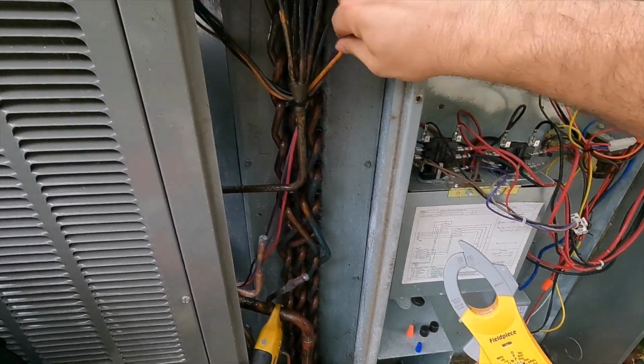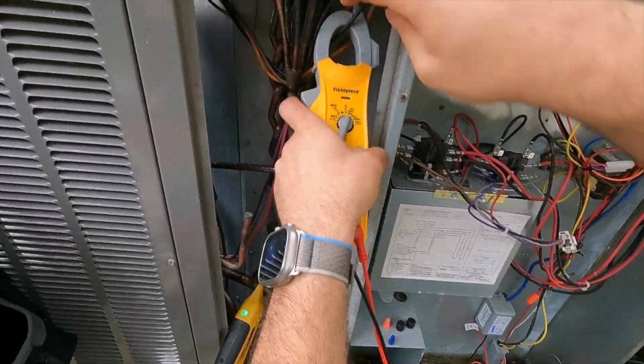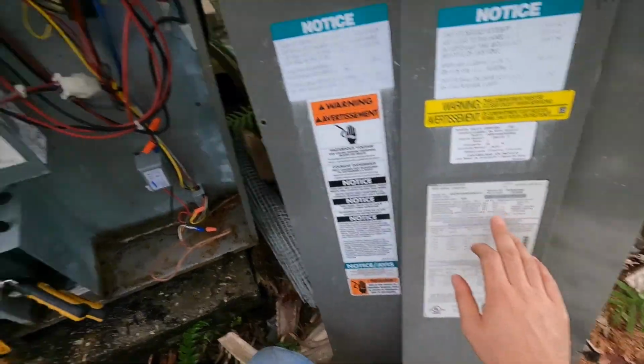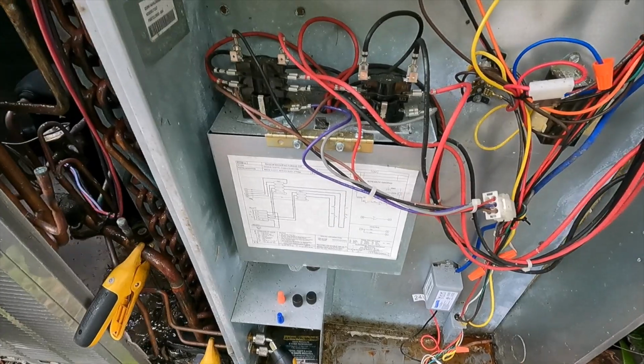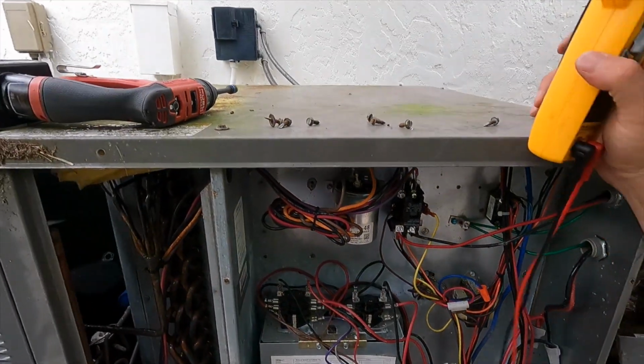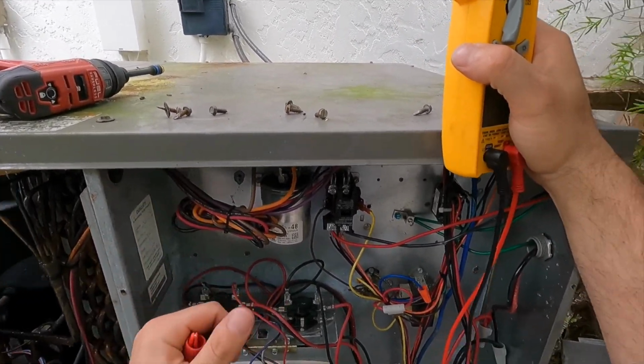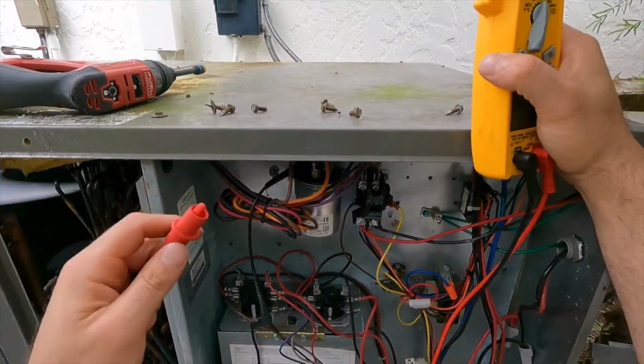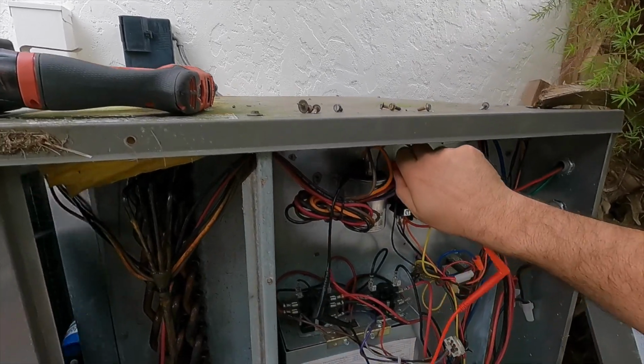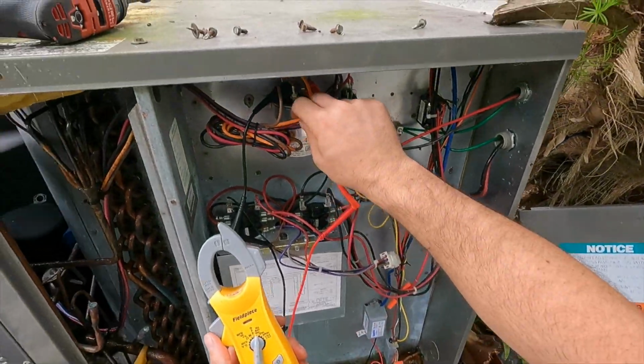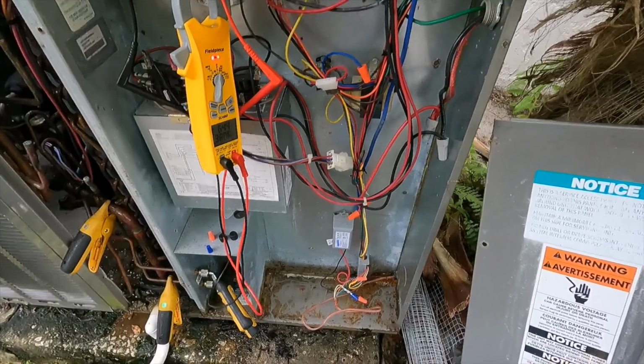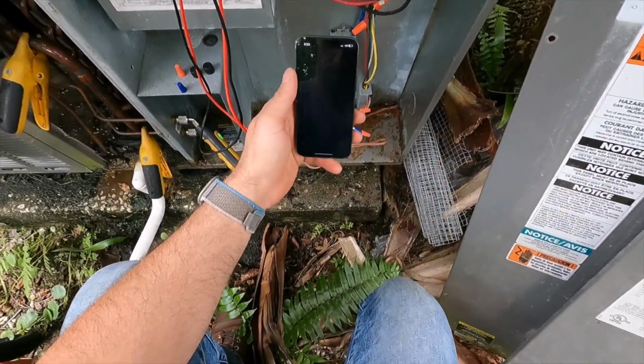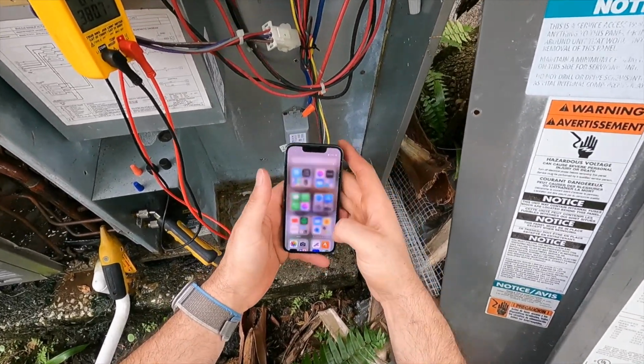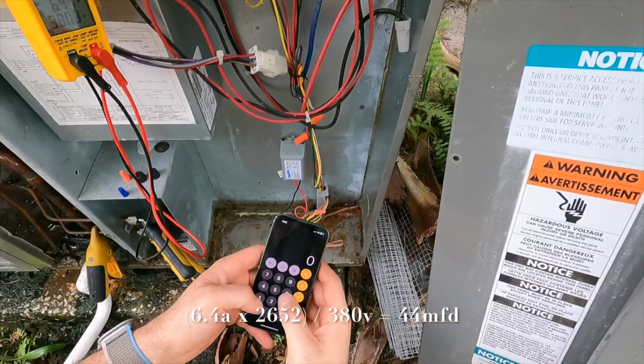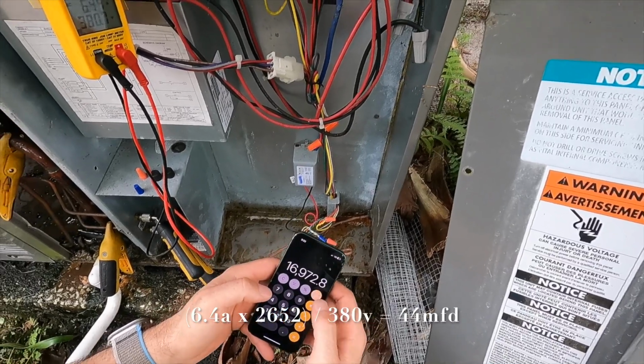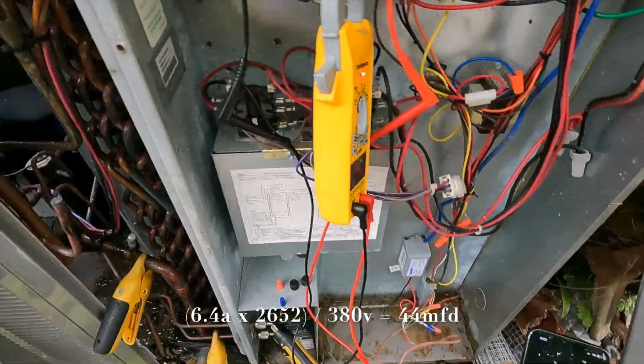Our fan. 1.5, 1.9. All right, let's check this capacitor under load. So we got a 45 plus 10 at 6% plus or minus. So let's see, this will be our common side and our compressor side. Careful not to get electrocuted. Now let's take that compressor amp draw and let's do a little bit of math here. All right, so we got 6.4 times 2652 divided by our voltage at 380. 44.6 to 45 microfarad capacitor.